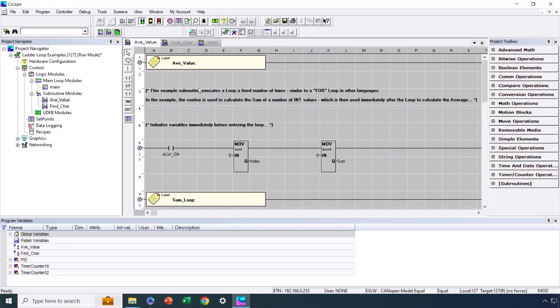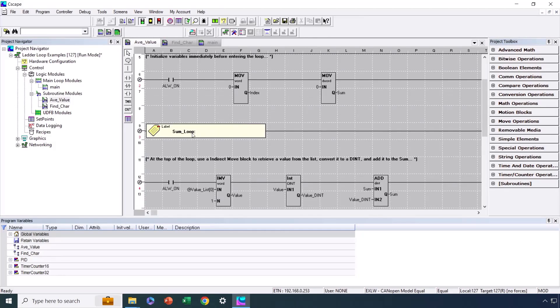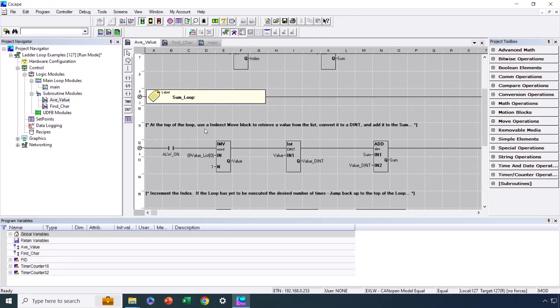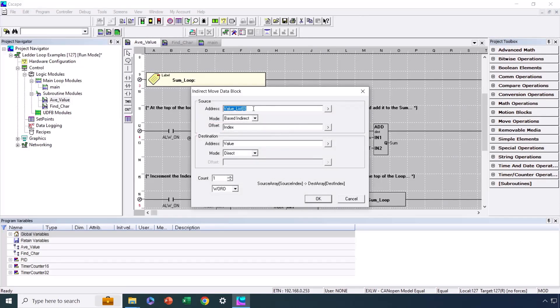Now let's look at the logic we have set up for our loop. Before the loop starts, we need to do initialization. We have a variable named index, which we will increment to keep track of how many times we go through the loop. We initialize our index variable to 0, and also initialize our sum variable to 0, as we will be using our loop to find the sum of 20 analog values stored in an array. Next, we have the label for the start of our loop, which we have named sum loop. At the top of our loop, we execute an indirect move to retrieve a value based on the index from the value list. We have 20 values, so our index needs to be incremented from 0 to 19 to point at the 20 different members of the array.